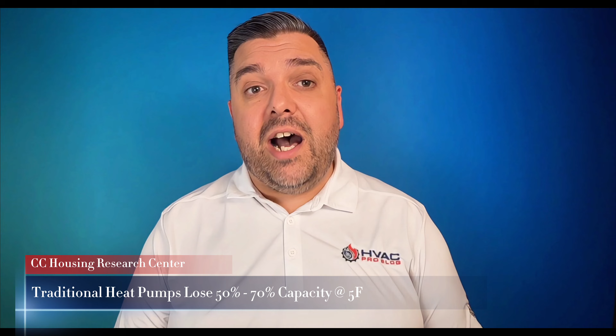Heat pump performance at low temperatures is another area where ignorance creates massive problems. Research from the Cold Climate Housing Research Center shows that traditional heat pump capacity can drop by 50 to 70% at 5 degrees Fahrenheit, compared to rated capacity at 47 degrees. Most contractors look at nameplate capacity and call it good. They don't check extended performance data. They don't calculate actual heating capacity at design conditions. Then they wonder why customers complain about auxiliary heat running constantly.